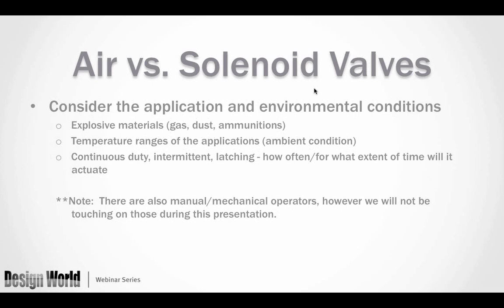You should also consider temperature ranges, whether the valve will be in continuous duty or continuously held in a position, and the fact that a coil will produce heat. Those factors can be compensated for in the design, but they are considerations when deciding between air and solenoid actuation. Many people choose solenoid today because of programmable controllers and electrical controls, where you'll need a solenoid to activate the valve.